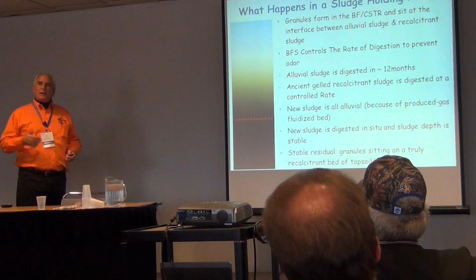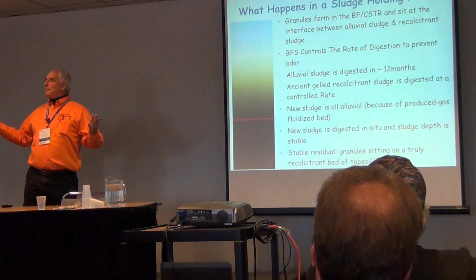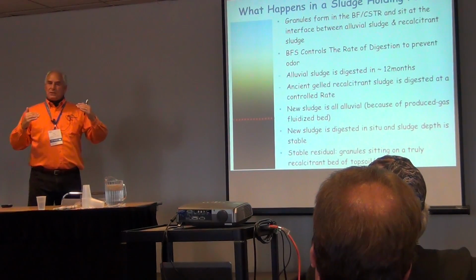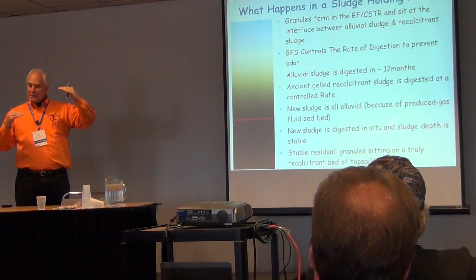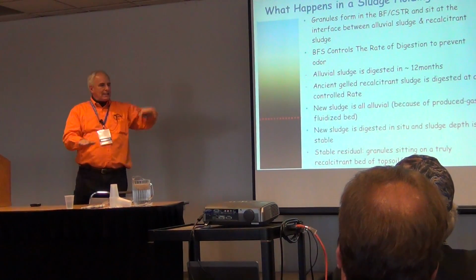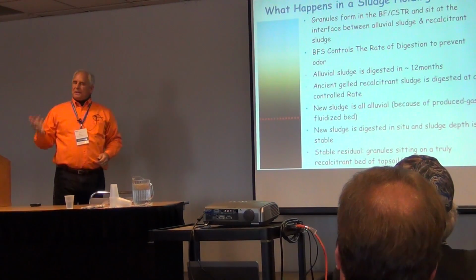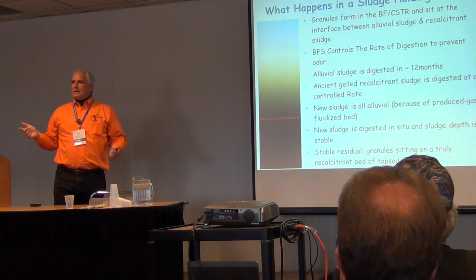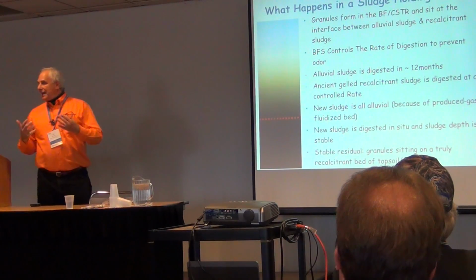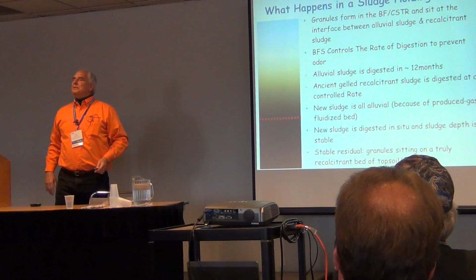Now, let me tell you why you don't want to do it fast. When you do it fast, you make a lot of gas. Now, how many of you know about pond turnovers? Of course, you all know about pond turnovers. But the pond turnovers are caused by density difference and wind pushing the water to one side, and then that gets higher than the other side and the pond flips. It's that simple. Most of you think that only happens in the spring and the fall when you have this temperature difference. But if you digest too fast, you make too much gas. What's the gas do? It leavens the entire column. And then you can have continuous turnovers.